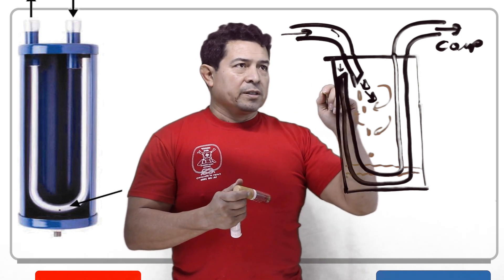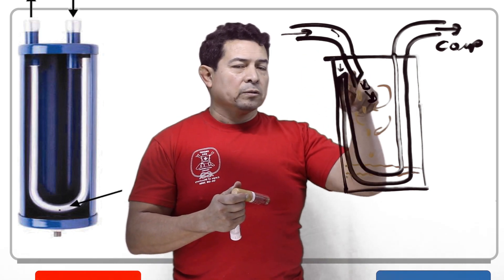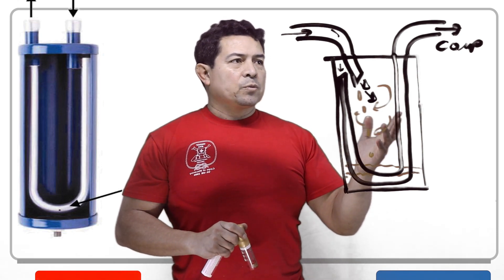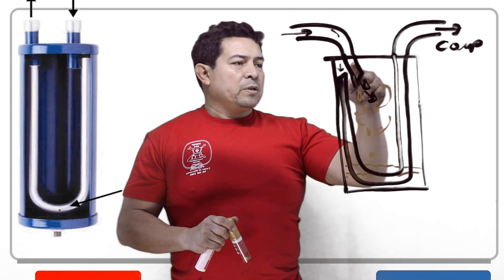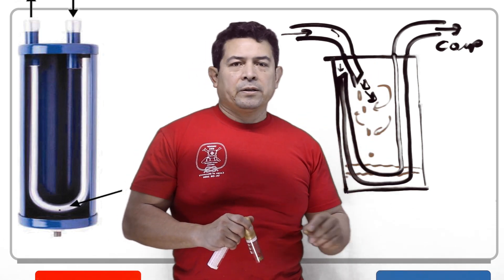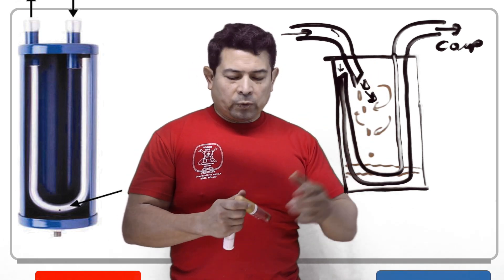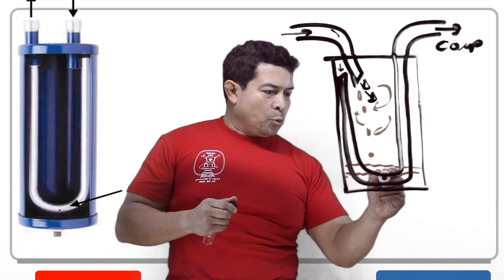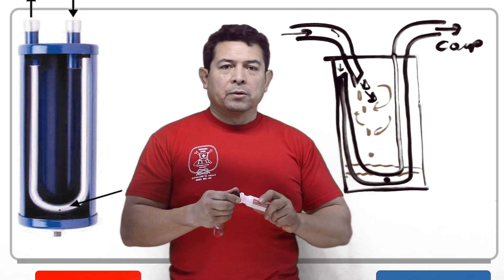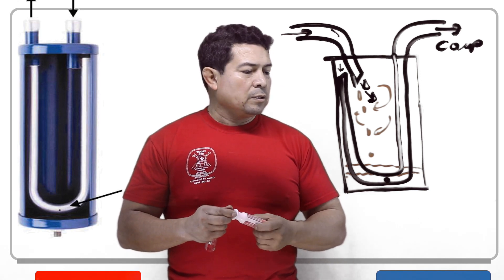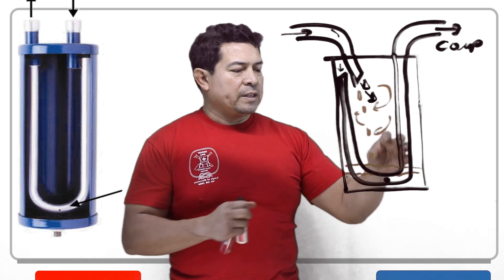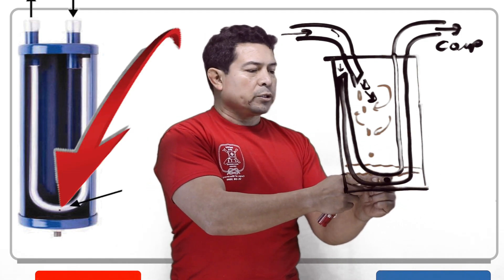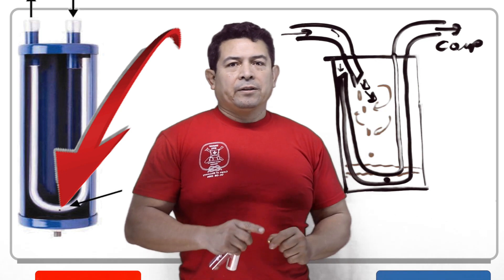Now, the problem with this is that oil always travels with the refrigerant — you can't help that, that's just what happens. When oil comes through here, the little droplets are going to collect down on the bottom. So what they do is they have placed a small port, a small opening, right there. So if there is any oil or liquid refrigerant in here, it's going to be sucked in through this little port and it's going to be going back out to the compressor.